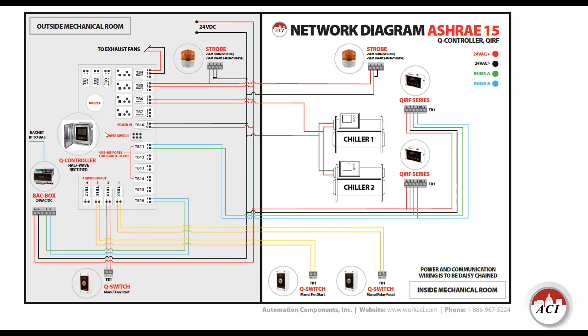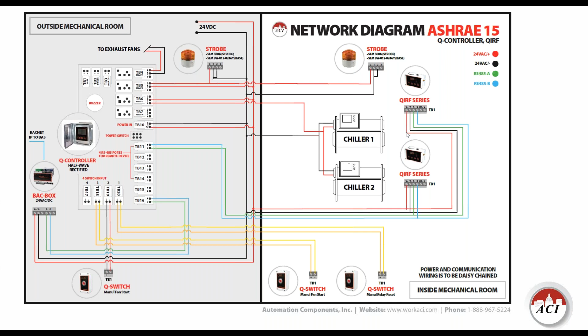This would be another example of a Q controller that's BACnet IP. Here'd be a situation where we have 2 chillers, but the 2 chillers have different Freons. And when you have different Freons, you have to have a QIRF for each Freon. You can't just do one and hope it works out. So it's kind of the same situation, with a strobe inside, a strobe outside, Q switches for override, and so on and so forth.